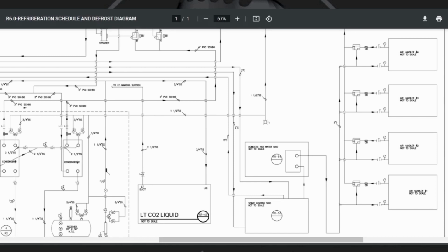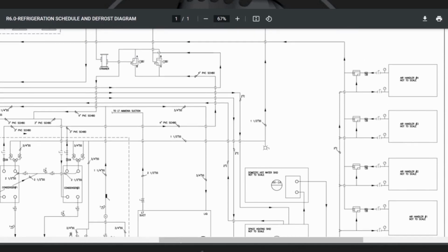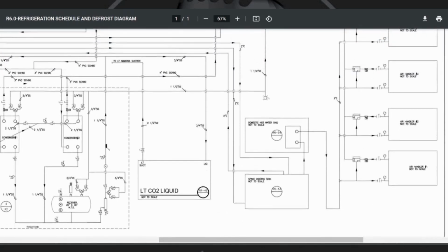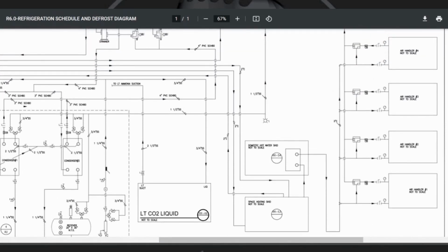So each of the small loads has a board and a glycol loop in the air handler. And when you want cooling, you turn the pump on, little circulator pump, and you move maybe, on a meat prep, you maybe move 5 GPM. On an office air conditioner, you might move 2 or 3. On each stage of the main air conditioning, we move 10 GPM. And it just goes through the air handler, it goes through the plate heat exchanger.